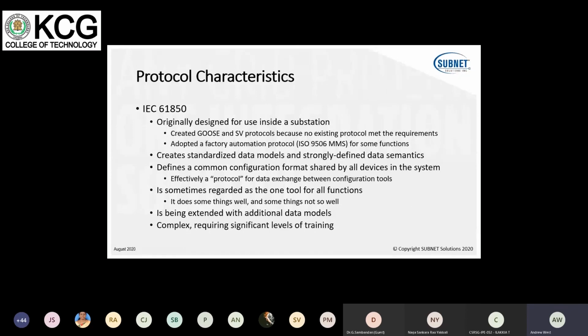That's an example. The real strengths of 61850 are the use of the data models with very strongly defined semantics and naming, so that all of the data is associated with a name and the name is strictly defined. So once you see the name of some data, you can understand what that data represents. That's a great strength. Another great strength is a common configuration format, the system configuration language, which is an XML-based configuration system, effectively a protocol for exchanging configuration data between the configuration tools for different devices, and allows the integration of all of the devices' configuration in a single system configuration tool, which is a real milestone, and it does help manage these hugely complex systems.